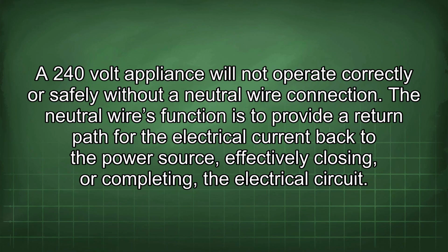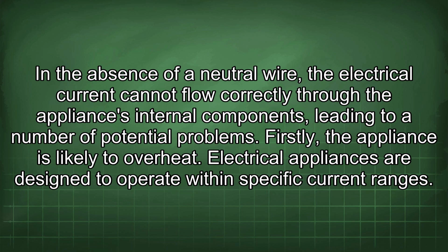A 240-volt appliance will not operate correctly or safely without a neutral wire connection. The neutral wire's function is to provide a return path for the electrical current back to the power source, effectively closing or completing the electrical circuit. In the absence of a neutral wire, the electrical current cannot flow correctly through the appliance's internal components, leading to a number of potential problems.